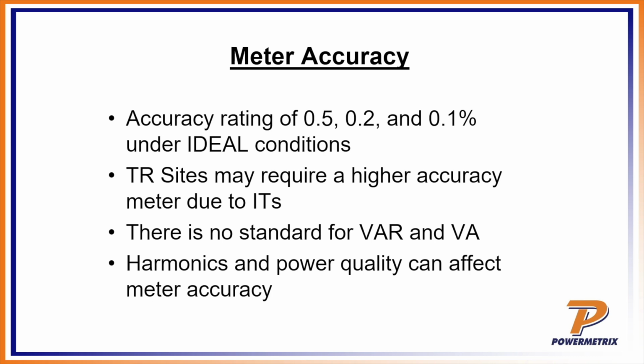Because that's the other consideration: how accurate do you want the meter? The accuracy ratings are 0.5, which is typical on your resi meters, and then you have 0.2 or 0.1 on your electronic meters that are transformer rated. And the self-contained can get up there too, but 0.5 is a typical resi accuracy. The transformer sites may require a higher accuracy meter due to the instrument transformers. Because my instrument transformers are providing me that accuracy, transformer sites may require a higher accuracy meter.